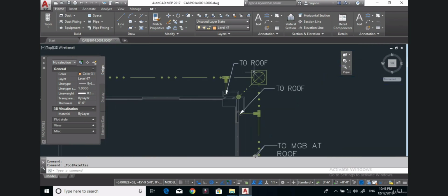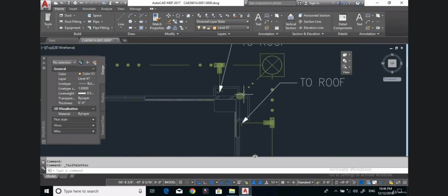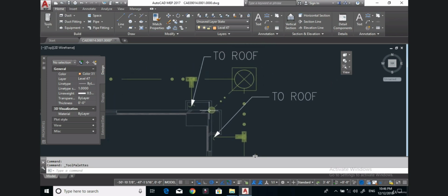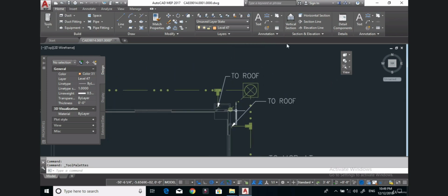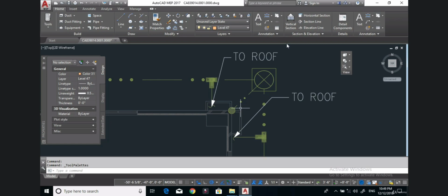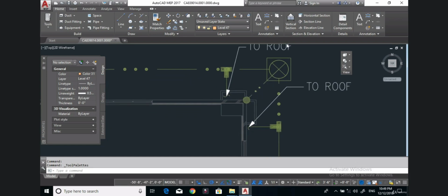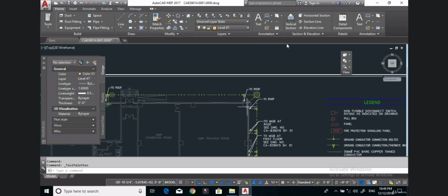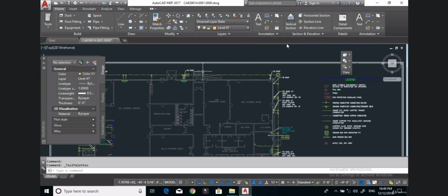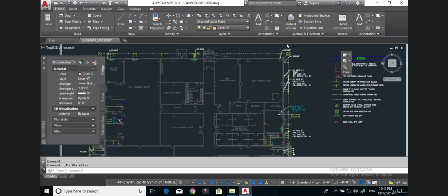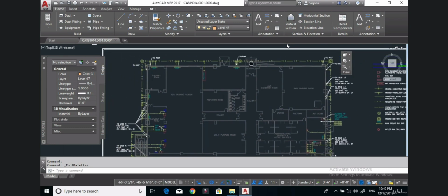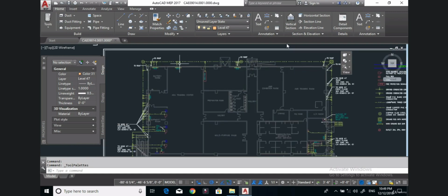And from the corner column also I make here in the corner, he connects this conductor to the structure of this column. This is a foundation grounding, you remember, and also for this loop of the 120 mm copper cable, in addition to this rod, what is the type of this grounding? Of course the circular grounding.